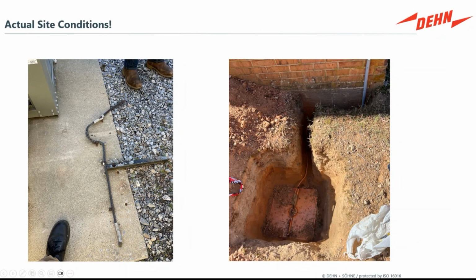There's things like the copper cable, although it looks very, very robust, it's directly embedded in the concrete without a suitable insulated plastic conduit or covering, where the water and the concrete and the copper all mix with oxygen. That's going to be a very key area where it's going to erode over time and lead to exactly this, a broken grounding connection.